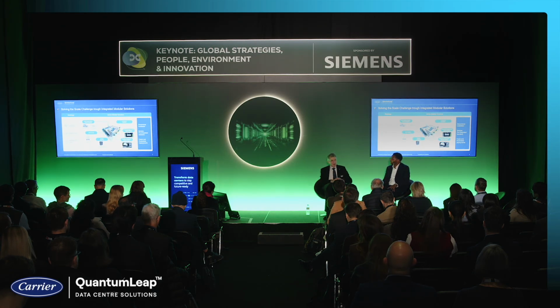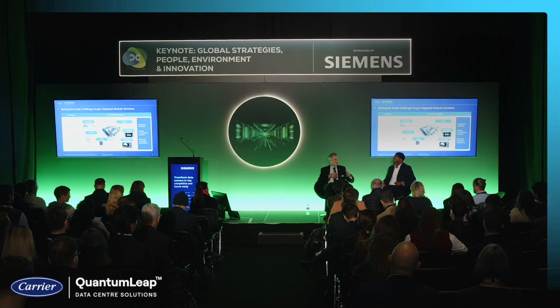There's also what I call maybe supply chain, but maybe we should say organization of build of data center, which is very important. With traditional lower density, lower capacity data centers, it was acceptable to do, for instance, one week of commissioning for the chiller. When you have 100 or 200 chillers on the roof, you cannot afford 20 weeks or 100 weeks of commissioning.